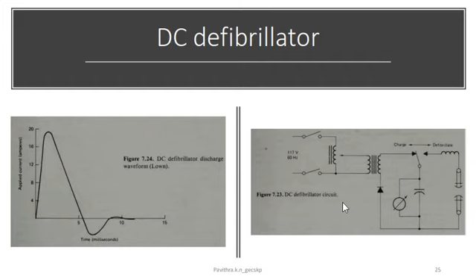The amount of electrical energy discharged by the capacitor may range between 100 and 400 watt-seconds or joules. The duration of the effective portion of the discharge is approximately 5 milliseconds. The energy delivered is represented by the typical waveform shown in this figure. The area under this curve is proportional to the energy delivered by the capacitor. The peak value of the current is nearly 20 amperes in this case, and the wave is essentially monophasic since most of its excursion is above the baseline.